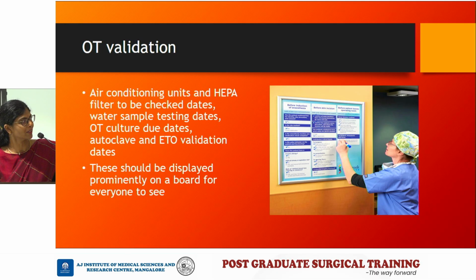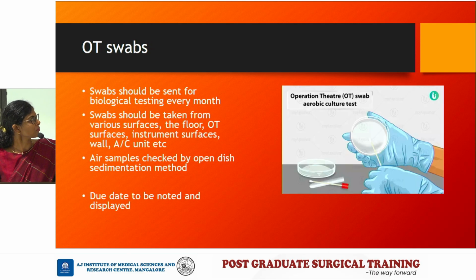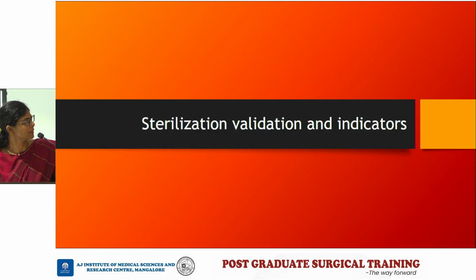Now all these dates ideally should be displayed prominently outside the OT somewhere on a board for everyone to see. So even before you enter the OT, it is better to have a look at it and make sure that you're going into a validated OT before you start the OT. And OT swabs ideally should be sent for biological testing every month. They should be taken from both sterile and unsterile surfaces. So the floor, the OT surfaces, wall, AC unit, everything. Air samples also need to be checked by an open dish sedimentation method. And again, the due date needs to be noted and displayed.